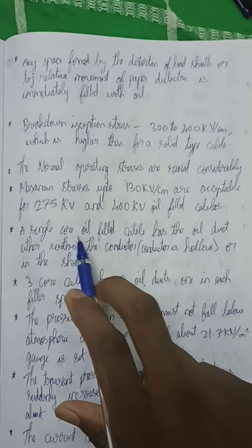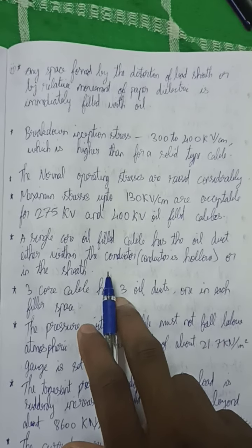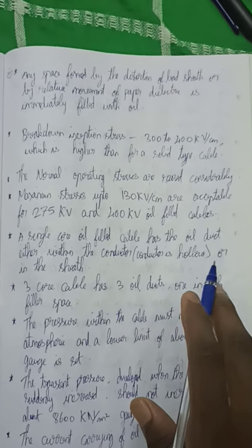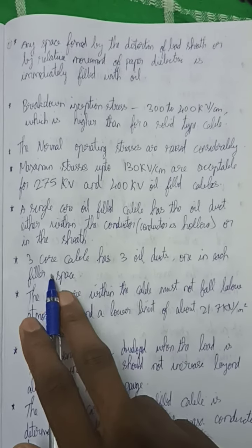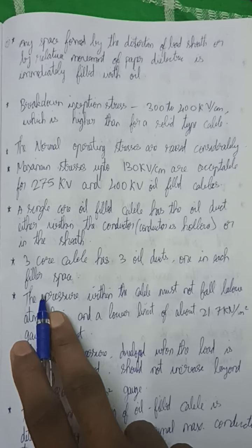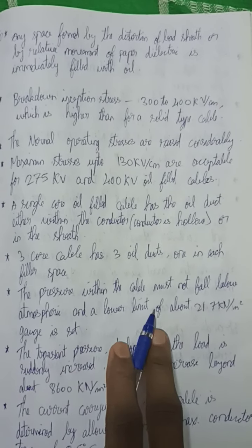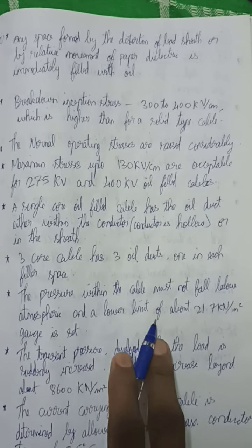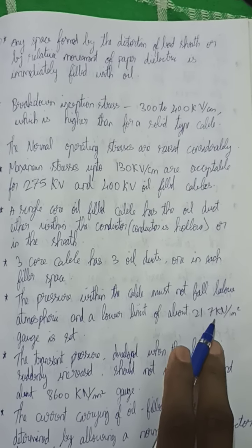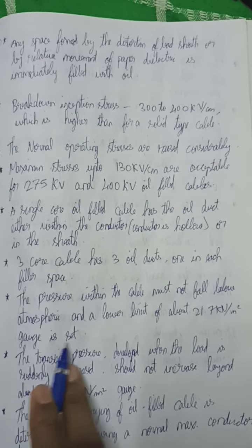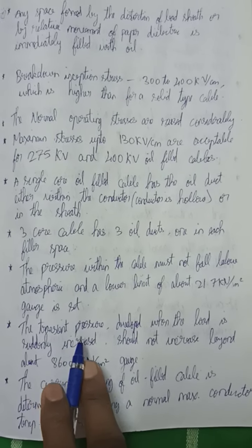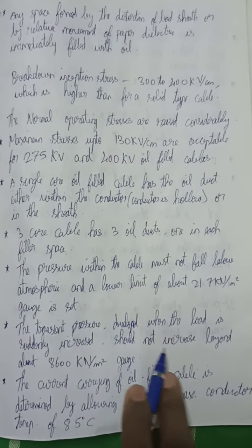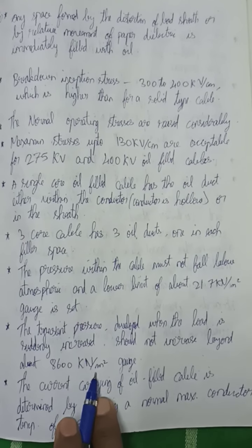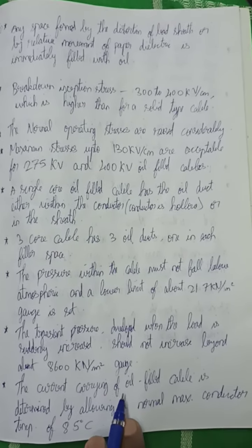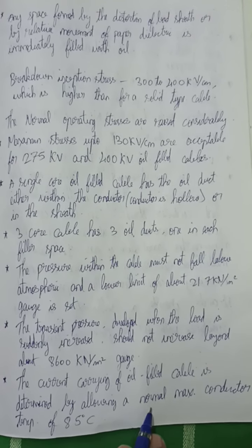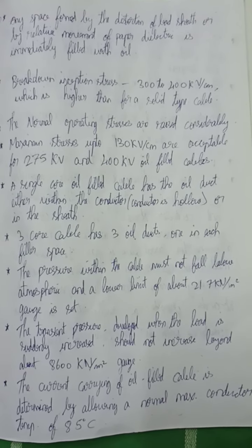A single core oil filled cable has the oil duct either within the conductor, where the conductor is hollow, or in the sheath. A three core cable has three oil ducts, one in each filler space. The pressure within the cable must not fall below atmospheric, with a lower limit of about 21.7 kN/m² gauge. The transient pressure developed when the load is suddenly increased should not exceed about 8600 kN/m² gauge. The current carrying capacity of an oil filled cable is determined by allowing a normal maximum conductor temperature of 85 degrees Celsius.